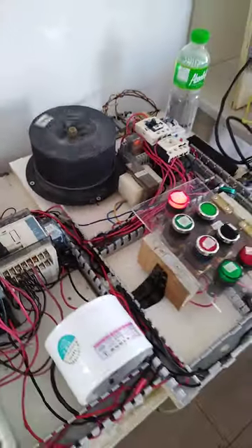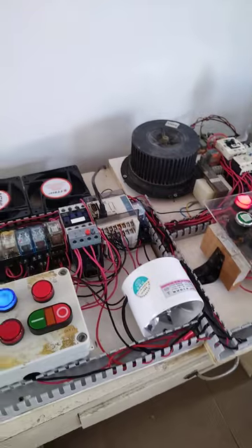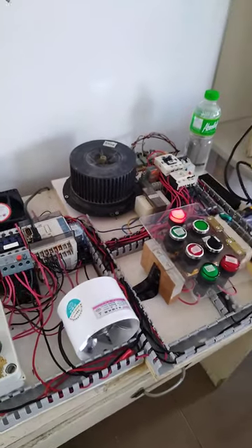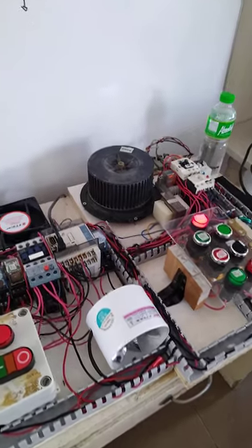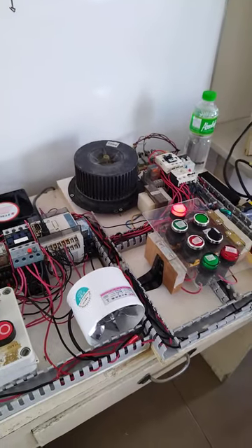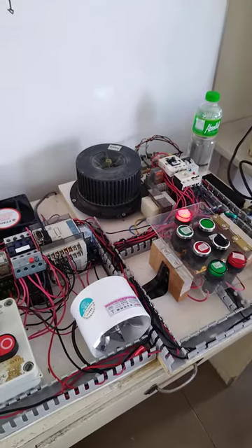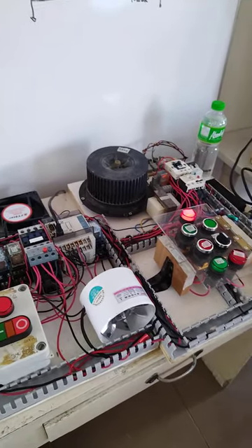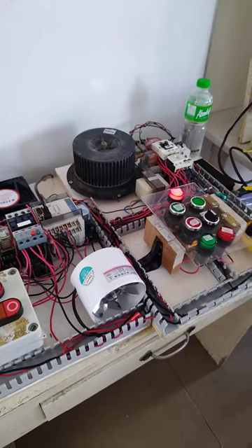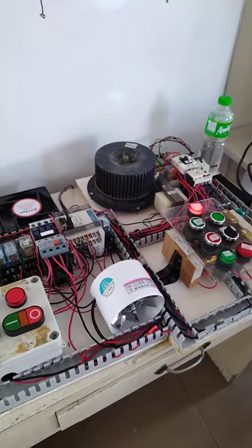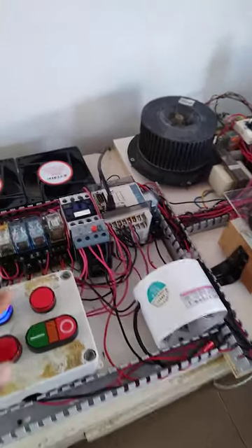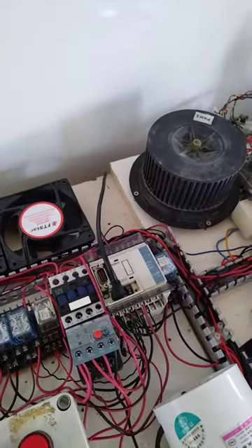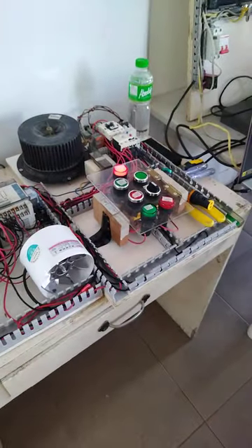So guys, thank you for watching and I do hope we are giving you some idea how you are going to solve problems if you are the control engineer in a building or in a plant. Now basically, you will encounter this problem during fire scenario because these big fans might start simultaneously. Now if you don't have a PLC to control those fans, then maybe you can install an on delay timer.